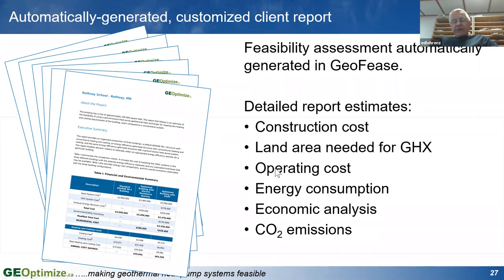And one thing, with the work that we've done with Otter Tail Power over the last number of years, when you compare the size and cost of the ground heat exchanger based on typical rules of thumb that are used before anybody's done any kind of energy modeling, we've typically been able to reduce the size and the cost, if we've had the opportunity to work with the architect, the building owner and the mechanical designers, by anywhere between 35 up to as much as 65%. That has a huge impact on the economics, return on investment, the simple payback, however you want to look at it.